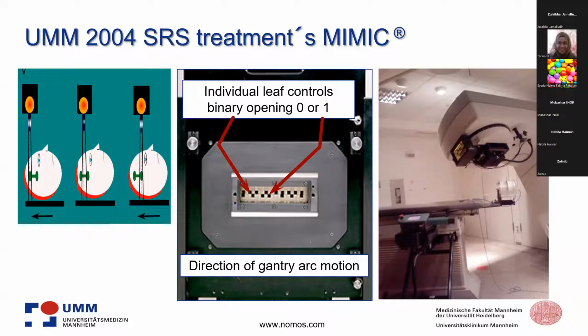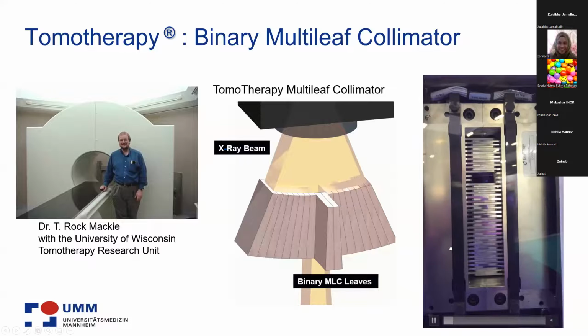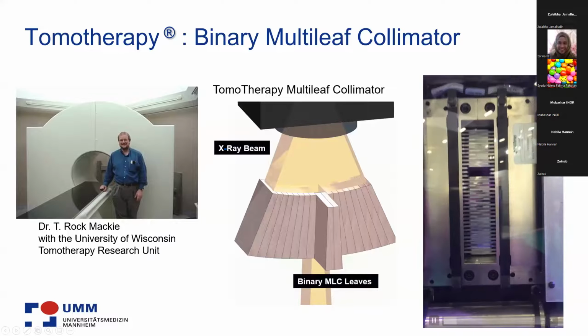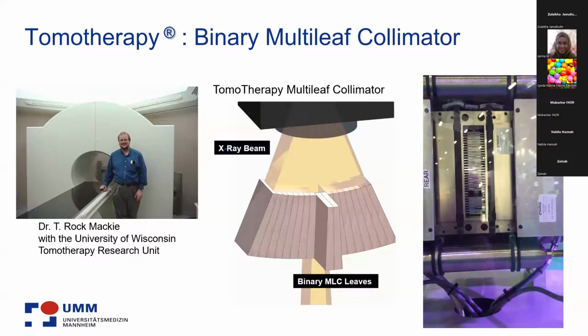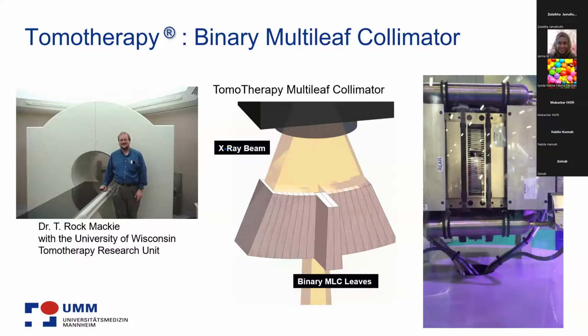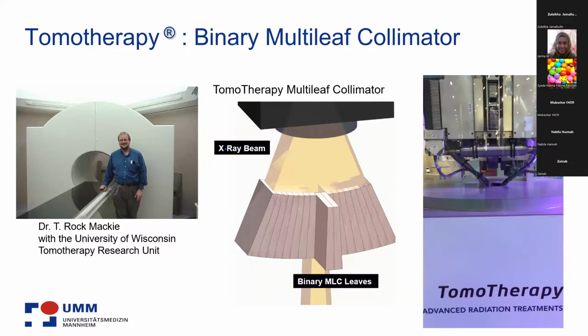And in that case, this is the same thing as the binary multi-leaf collimator. You know this from the Tomotherapy. Hopefully you could see this movie. I have taken it at the ASTRO from this collimator. You see there is only 0 or 1. That means you could deliver a very high modulation. There is no moving of leaves within the treatment, and this is an advantage of this method.